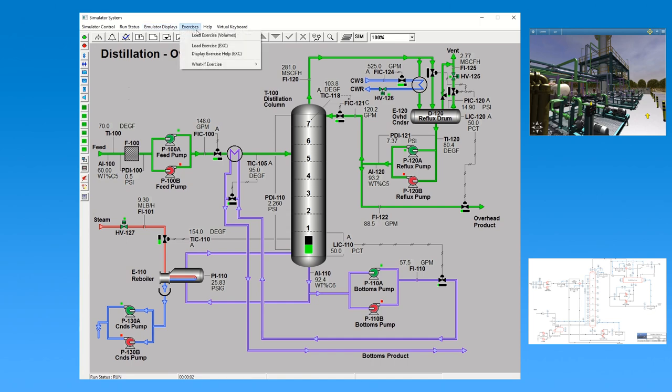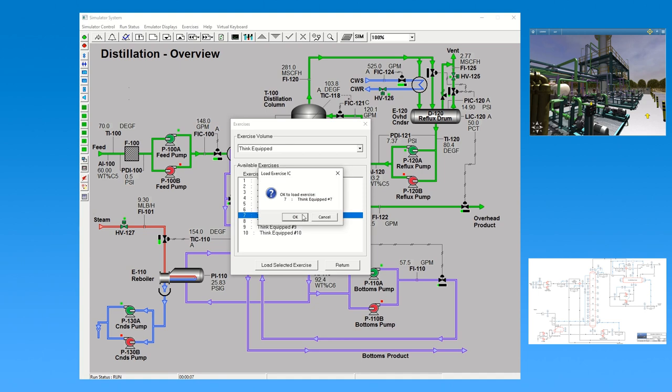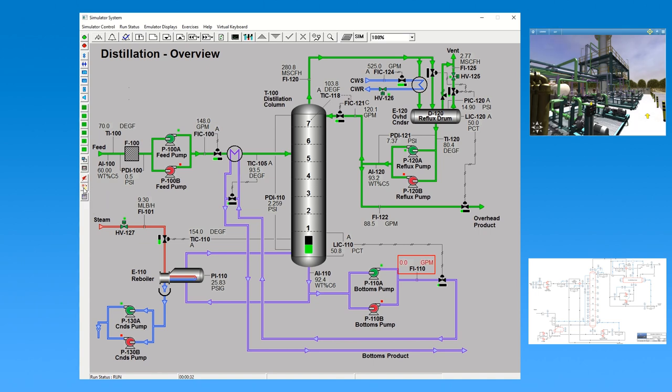Let's take a look at an example. Unknown to the trainee, the instructor introduced a fault that appeared at a predetermined point after starting the simulator. An alarm is initiated, indicating zero flow at the bottom's pump.